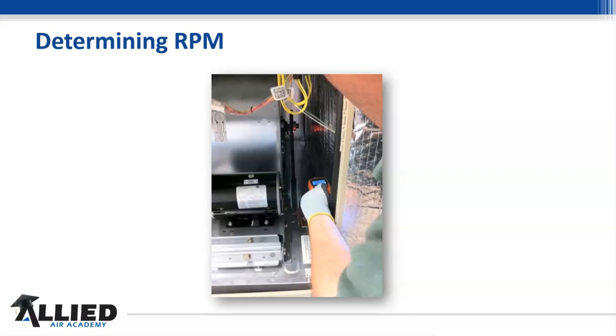There's a couple of things here to keep in mind. Number one, let's go back and talk about the RPM range. When we take the door off the side of this unit, this thing's going to load up with air, and that's going to affect your RPMs. So one of the things to do is get the door and cover up as much of the opening as you can, and still get in there to tach the motor. That way, if you're within that RPM range, and I always encourage people to try to get mid-range of that RPM range, when you put the door back on, you won't go over and you won't go under. And I'll show you how to adjust the motor in just a few minutes. But that's one of the best ways to do it here.